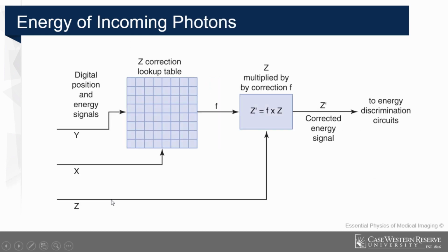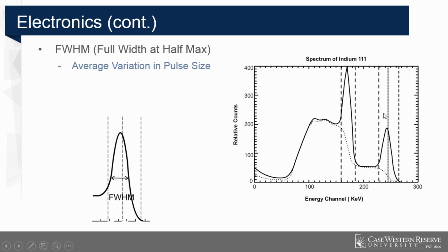Separately, there is another channel to determine the energy of the incoming gamma photon for further processing by this unit called PHA, pulse height analyzer. It will be able to discriminate the energy of the incoming gamma photon. When you have everything, you can plot your spectrum. So here is a spectrum, and it shows the energy of the gamma photons as determined by PHA.